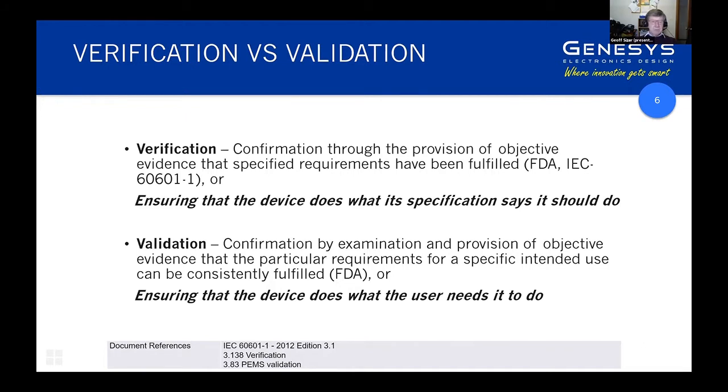So in a nutshell, the verification is a formal process that is against the device specification, and also tests defined in 60601-1, for example, whereas the validation is against a plan that needs to be constructed to provide adequate evidence via the clinical trials and usability trials process that the device does satisfy those user needs. So we'll be touching on that in a little more detail as we go along.